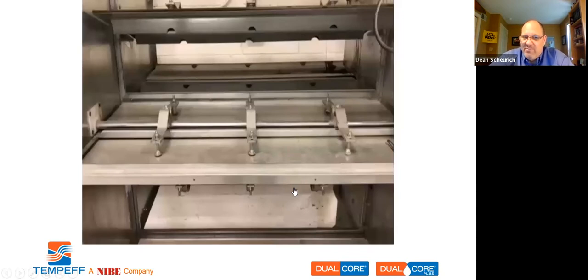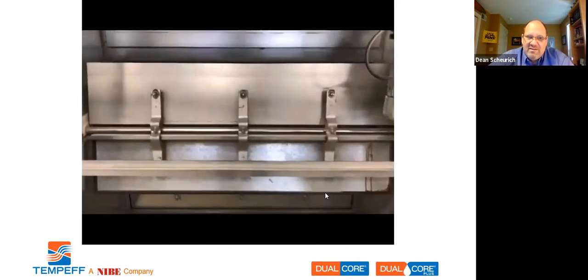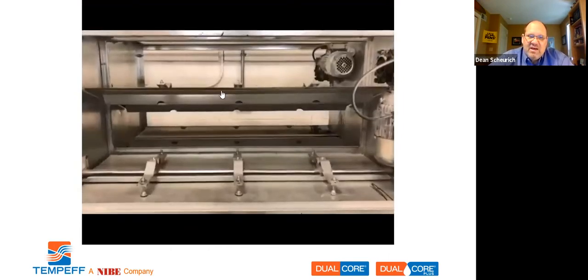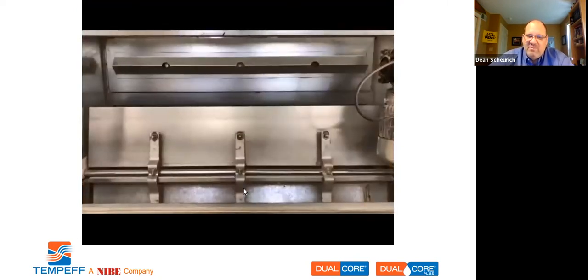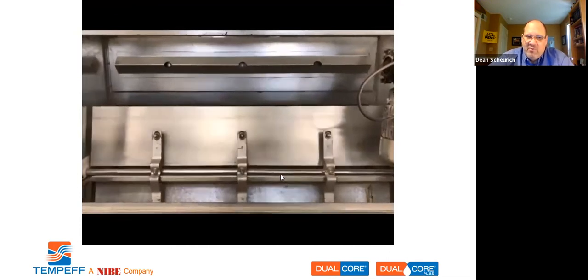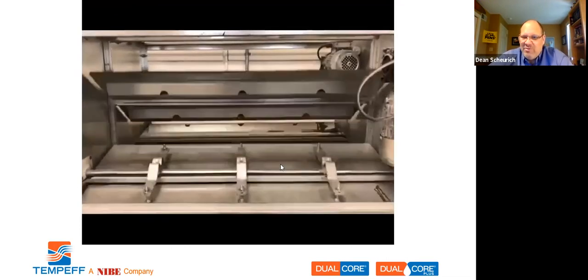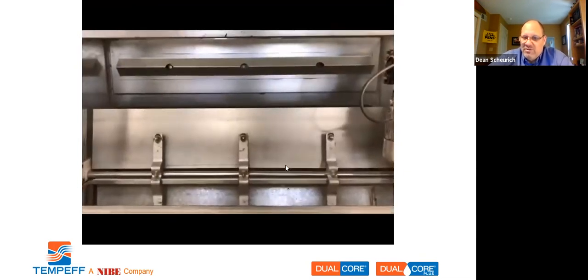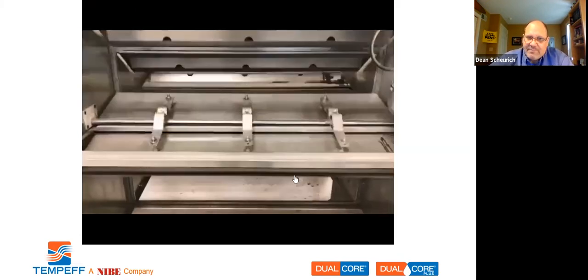You then have the dampers. Fans do not stop running. Supply and exhaust run. The dampers are top and bottom compression seals. They're dual plated. There's bridges on them because we want to make them as light as possible on the unit, and we want them to obviously seal. I think at 3 or 4 inches of static, when these dampers are closed, we have less than 1% of leakage on those. So that's what those dampers and that system looks like.